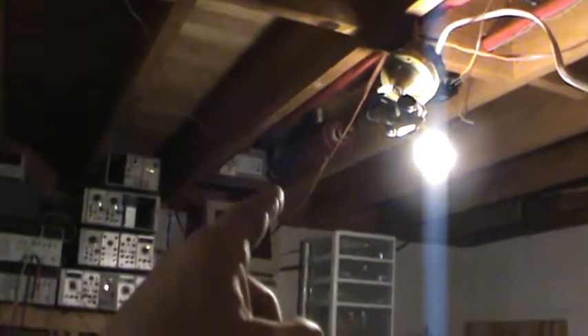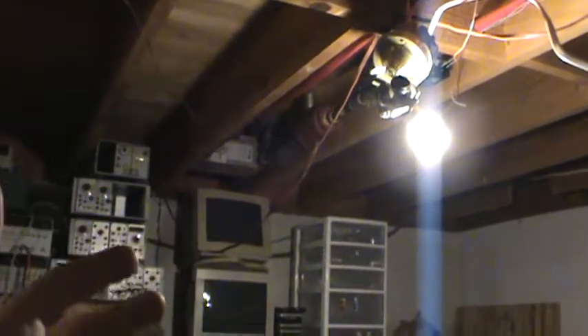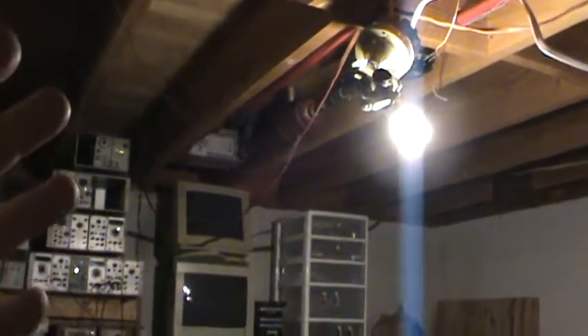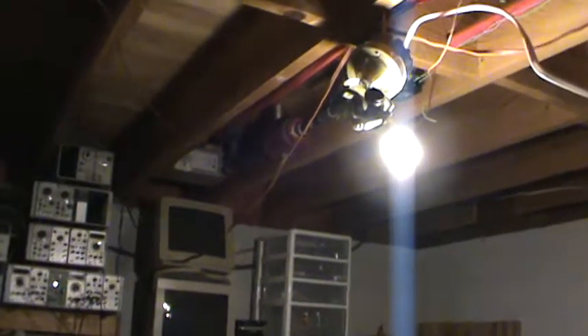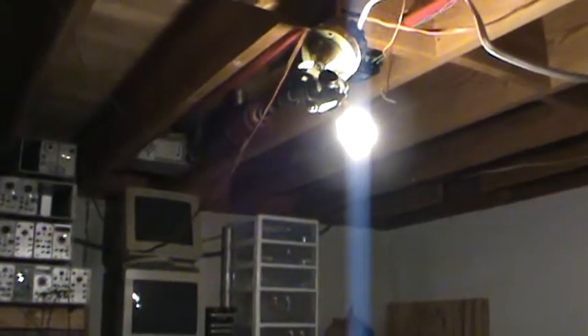Now, you may say, well, why would you want to do that? Why wouldn't you just idle the boiler? If you don't need heat in the home, just don't turn on the fan and the fire in the boiler and let it sit there. Well, the problem with that is that when the boiler is running but doesn't have full flow of air going in, it'll smoke a lot, and smoke is unburned fuel, and that's just fuel that I have to load and waste.